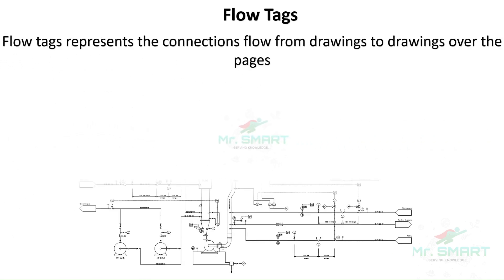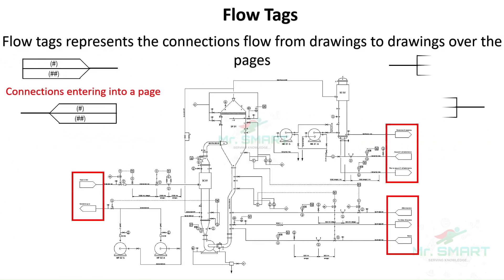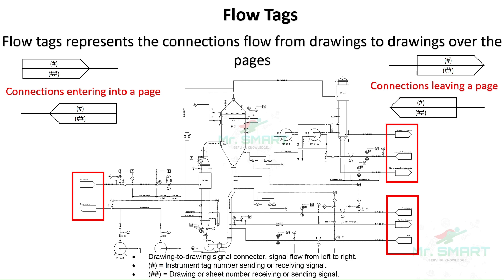Flow tags are the next important thing to know in P&IDs. A flow tag tells us the connection flow from drawing to drawing. They tell us both the connection entering into or leaving the page, with instrument tag and sheet number of its origin. With this, you can actually track the connections across the drawing and the entire P&ID of your plant.